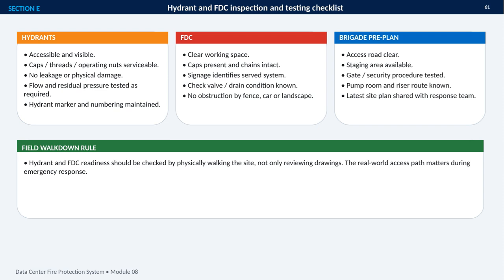For the FDC, the working area must be clear, caps and chains must be intact, and signage must identify the system being served. The check valve and drain conditions should be known, with no obstruction from vehicles, fencing, or landscaping. The brigade pre-plan completes the picture. Access roads and staging areas must be available, security procedures tested, and the pump room and riser route familiar to responders. The latest site plan should be shared with the response team. Most importantly, readiness must be verified by physically walking the site. Drawings alone cannot confirm the real access path during an emergency.